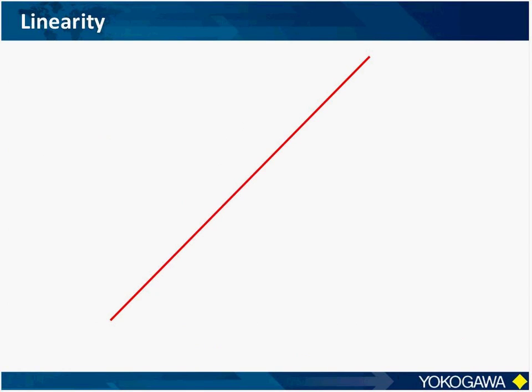Now, the correlation between the output of a vibrating element system versus gas density is very linear in nature. This allows the instrument to cover a very wide range of density values based upon a single calibration. The analyzer is capable of accurately interpolating and extrapolating density values within and beyond the scope of the calibration gases used. And what this allows us to do is to use very safe and inexpensive calibration gases that are readily available.